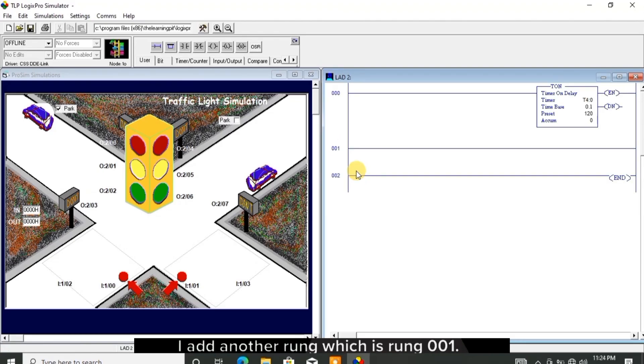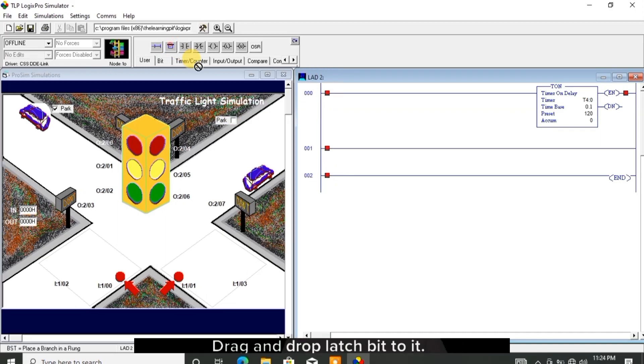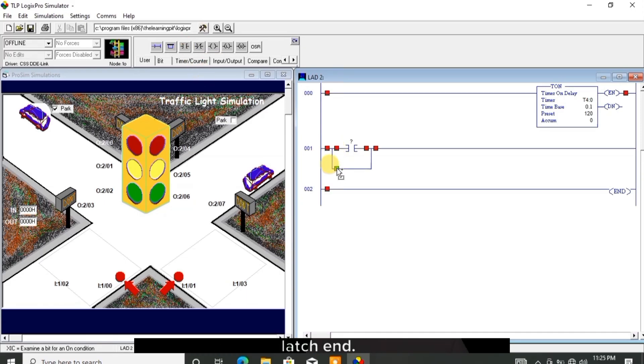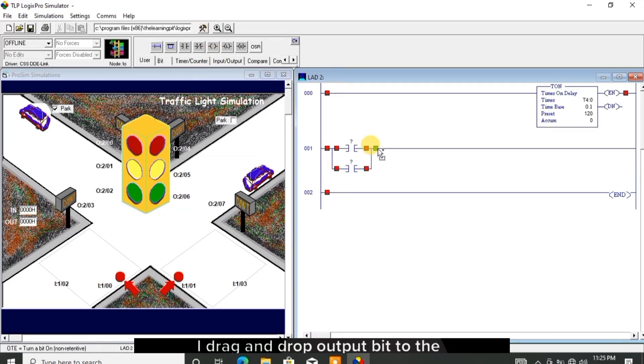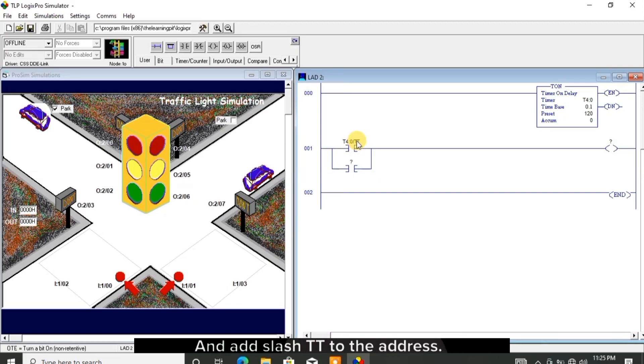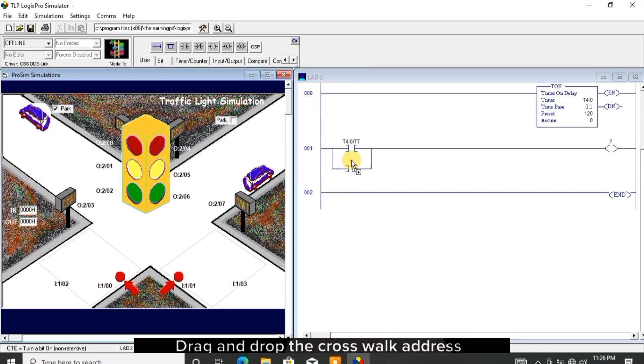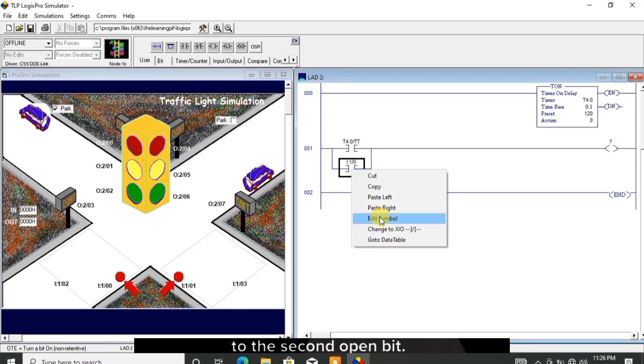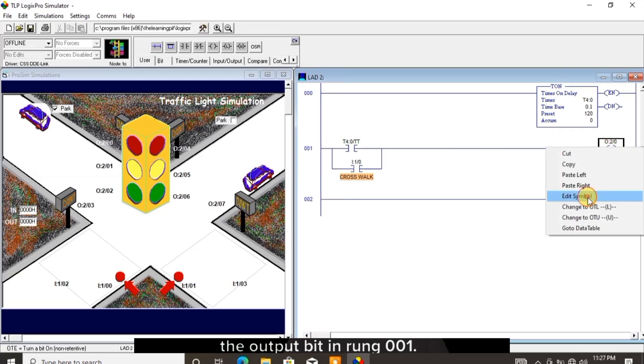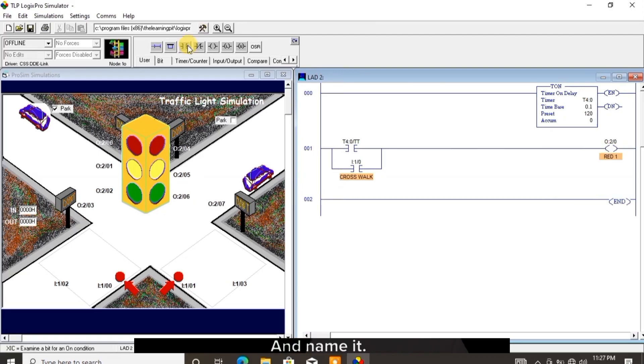I add another rung, rung 001. Drag and drop latch bit to it, drag and drop open bit to the latch, and another open bit to the latch end. I drag and drop output bit to rung 001. Drag and drop the timer address to the top open bit in rung 001 and add /TT to the address. Drag and drop the crosswalk address to the second open bit and name it. Drag and drop the red 1 address to the output bit in rung 001 and name it.